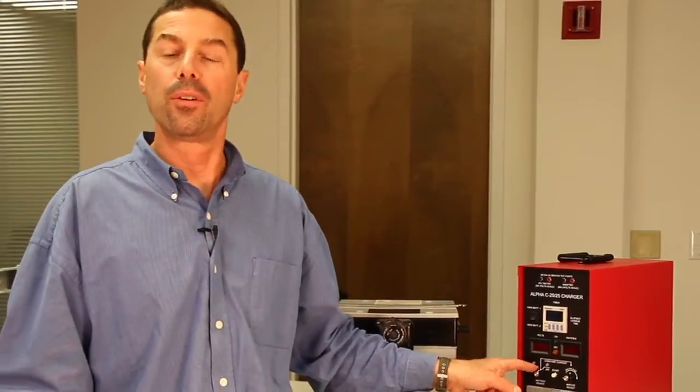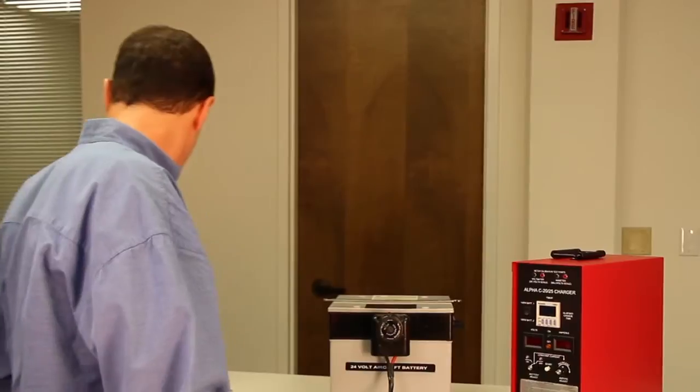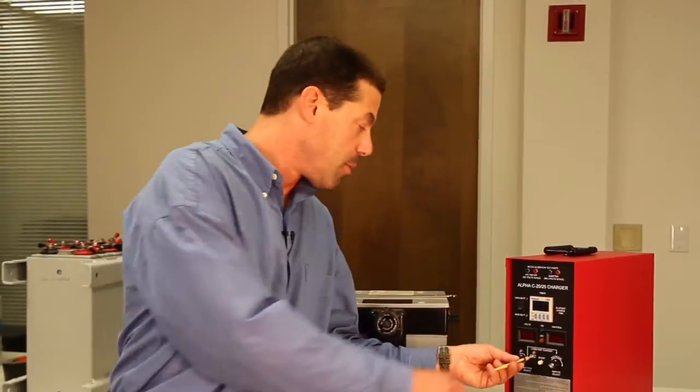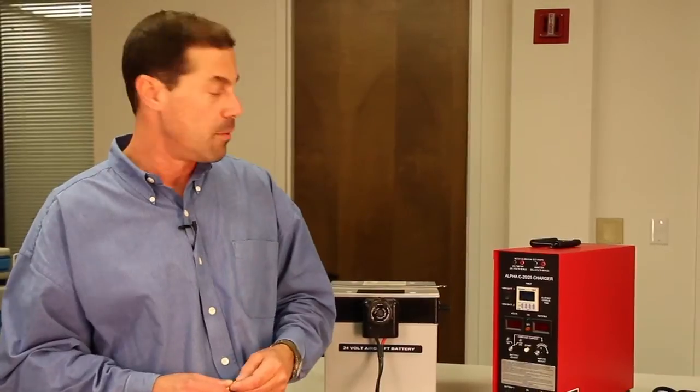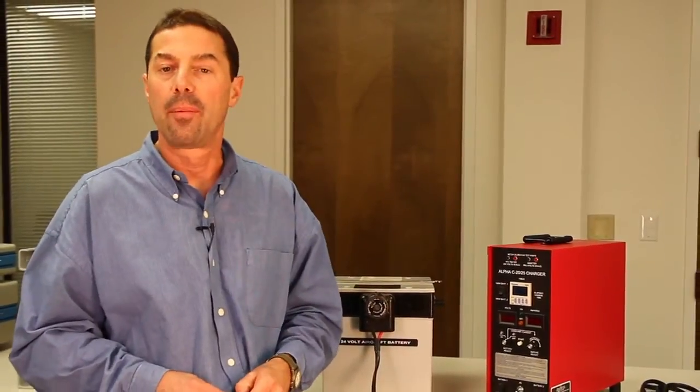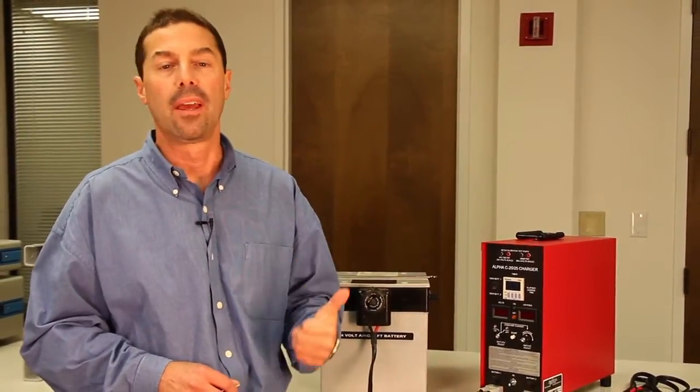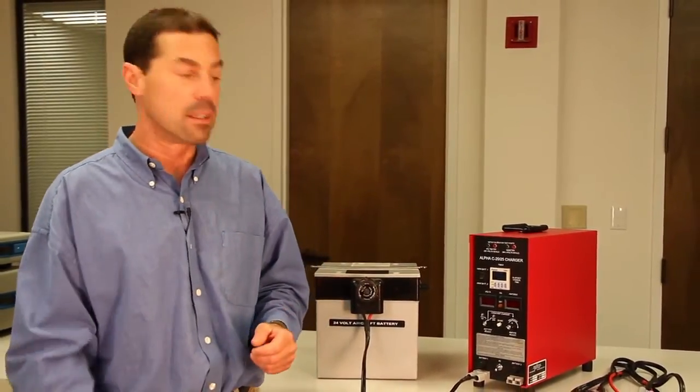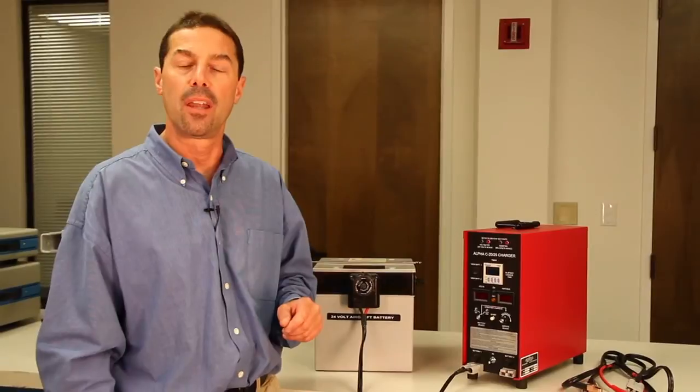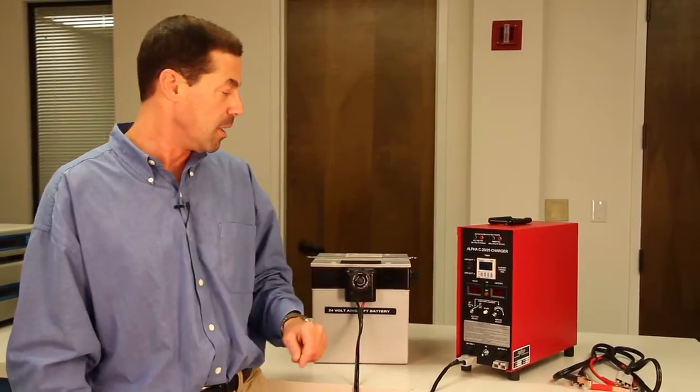You have end voltage trim. It can be done with a small screwdriver or a little tool. This allows you to set the end voltage for any particular battery manufacturer, whether it's a Saft, a Hawker, a Concord, or a Gill. They all have slightly different end point voltages, and this can easily accommodate those.